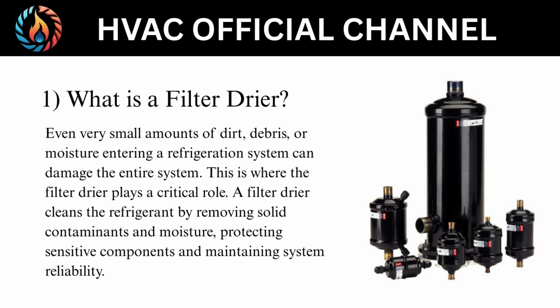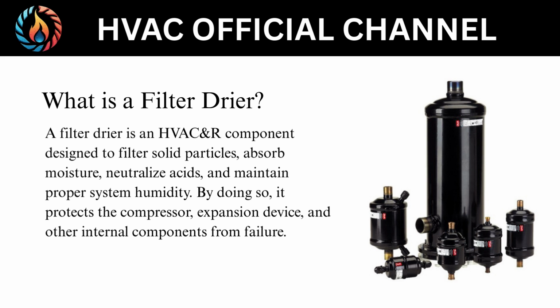Even very small amounts of dirt, debris, or moisture entering a refrigeration system can damage the entire system. This is where the filter dryer plays a critical role. A filter dryer cleans the refrigerant by removing solid contaminants and moisture, protecting sensitive components and maintaining system reliability. A filter dryer is an HVAC&R component designed to filter solid particles, absorb moisture, neutralize acids, and maintain proper system humidity. By doing so, it protects the compressor, expansion device, and other internal components from failure.